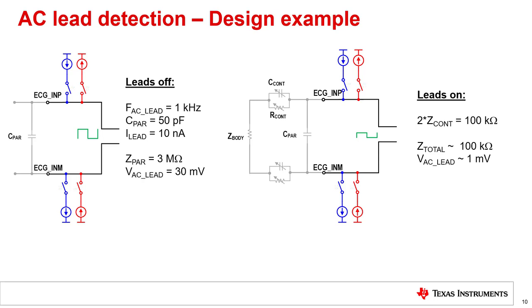Therefore, in a leads-on case, the strength of the 1 kHz tone at the ADC output is significantly lower than for the leads-off case, and this information can be used to determine the strength of the contact of the leads.